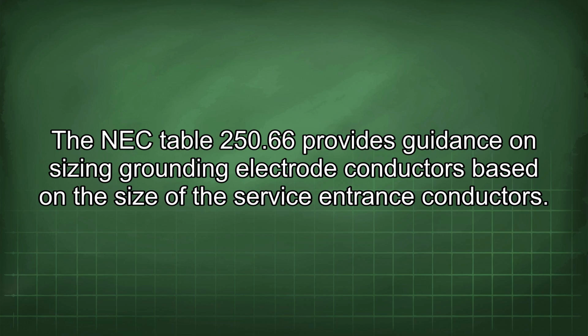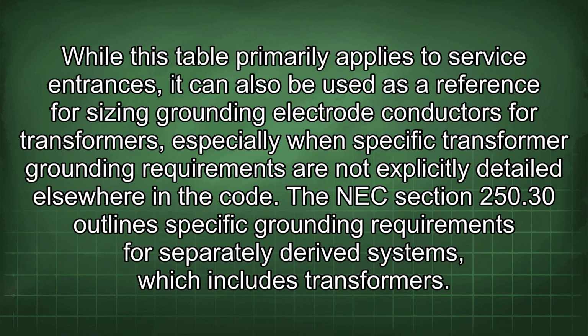The NEC Table 250.66 provides guidance on sizing grounding electrode conductors based on the size of the service entrance conductors. While this table primarily applies to service entrances, it can also be used as a reference for sizing grounding electrode conductors for transformers, especially when specific transformer grounding requirements are not explicitly detailed elsewhere in the code.